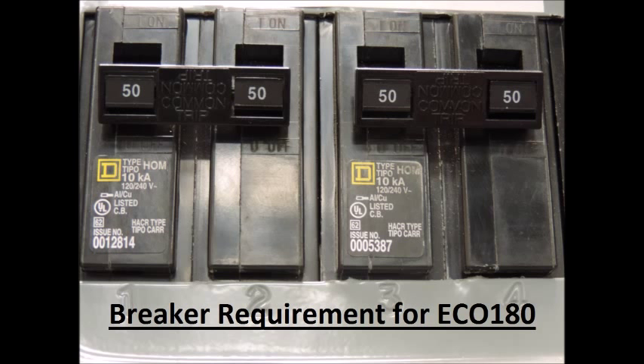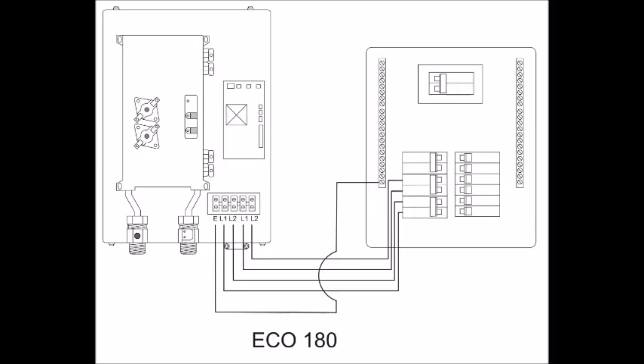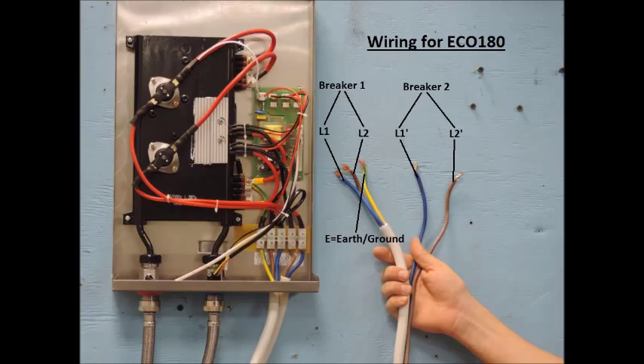Power for our ECO 180 must be supplied by two 220 volt double pole 50 amp breakers, giving the unit access to a total of 100 amps of possible power usage. Here is a simple line drawing of the power supply wiring for the ECO 180, and here is a real-world picture of the same model. Please note that each pair of L1 and L2 terminal connections should be wired to the same breaker.